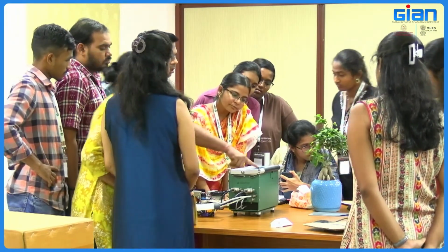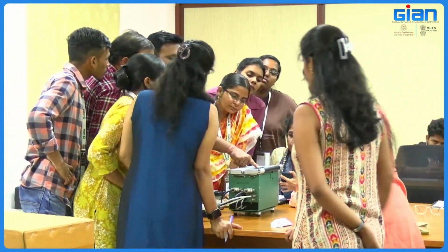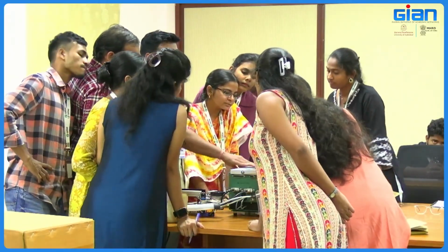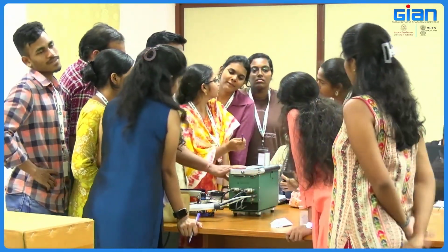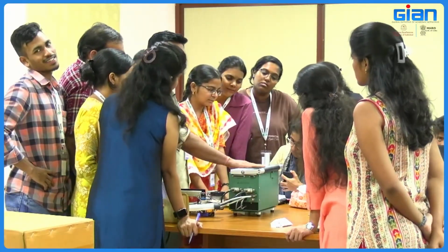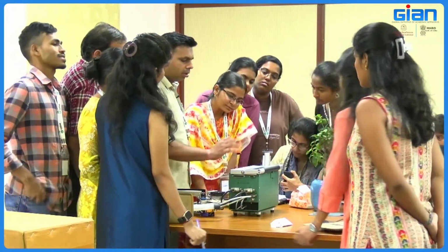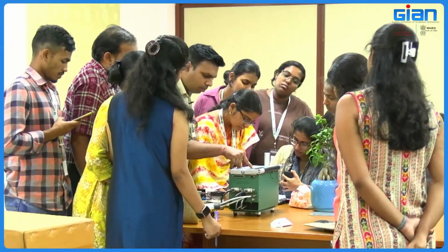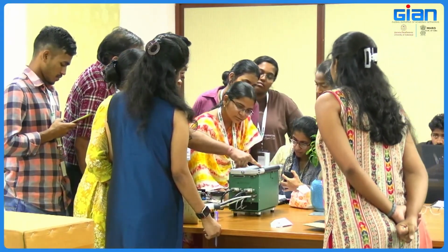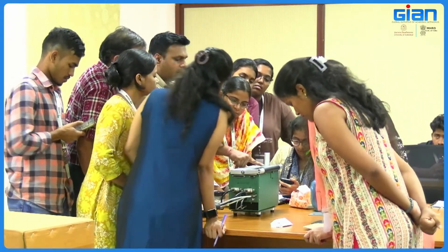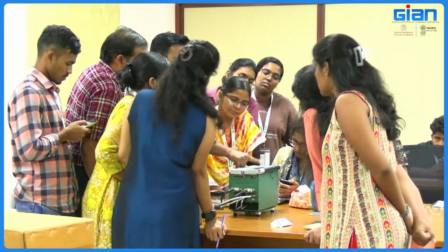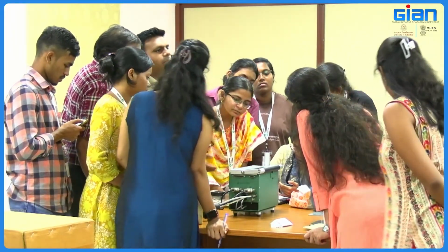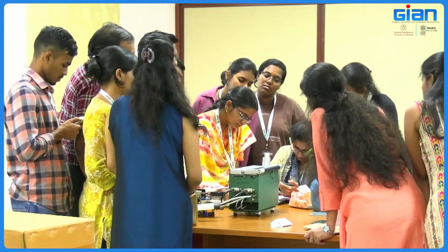Okay, now you see, the reference and sample CO2 are around 0. 0.0, 0.0, around minus 0.0, 0.1, even that sometimes happens. Got it? So once this is calibrated, you have to quit. Now if you press escape and go again to new measurements, you will see these values are almost similar. The reference CO2 and sample CO2 will be similar, and here the photosynthetic rate should not exceed more than 2 or 1. Got it?